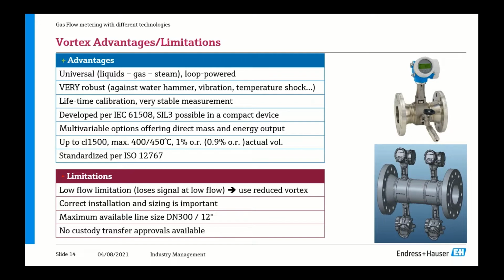And they are loop powered, so a perfect fit when replacing an existing DP flow meter with something better. It's very robust against water hammer, vibration, and temperature shock, so also a perfect fit for steam. It offers lifetime calibration, so we're getting meters back after 30 years in service, and they still show the same calibration factor as when they left the factory. They're also very robust against vibration. We are replacing competitors where customers say they had an issue, and using our Prowirl 200, those issues are just gone.